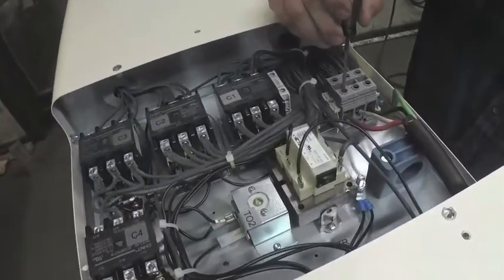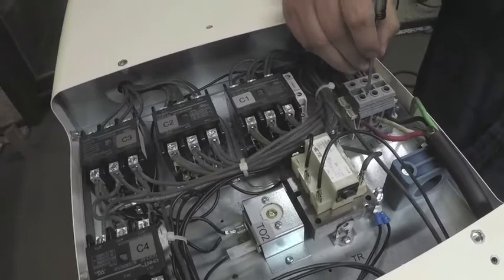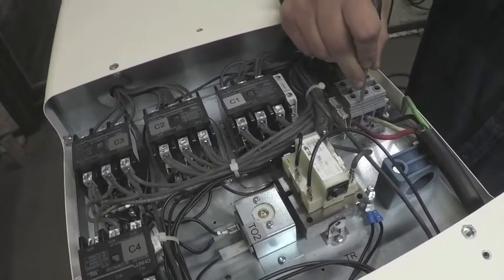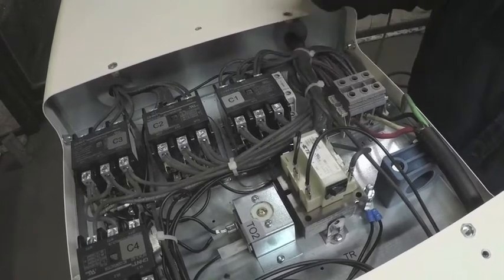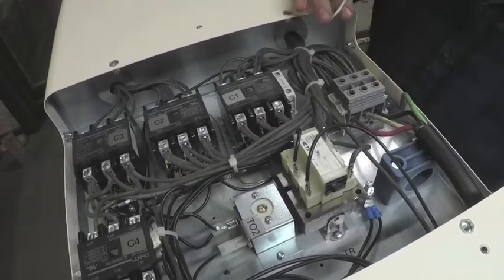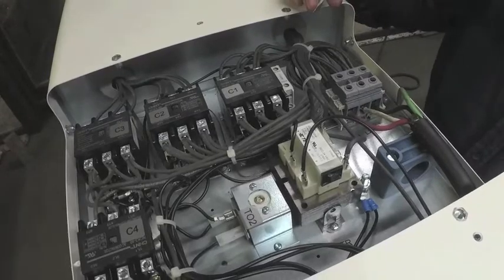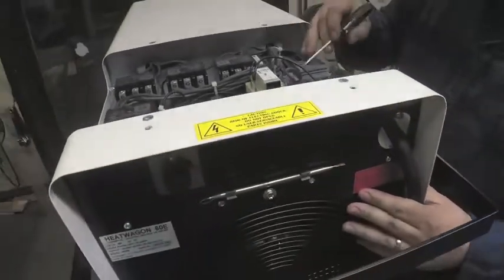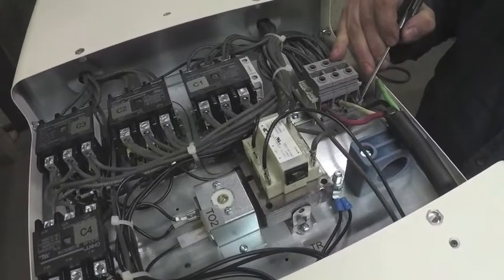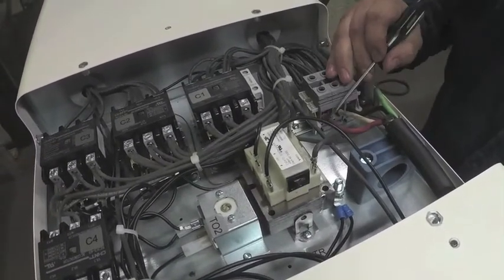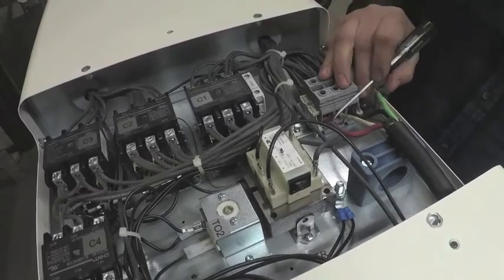When installing your 480 to the terminal block and firing up, if the heater is blowing air out of the intake of the heater, you need to reverse your two hot leads. If you do not, that will cause a problem with the heater and you need to repair it.